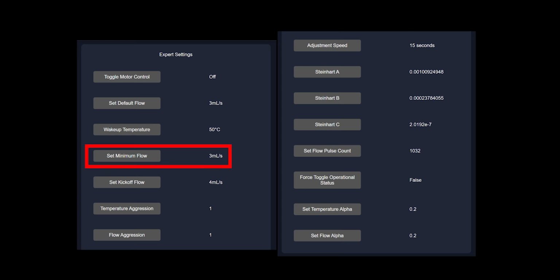The minimum flow is a hard limit where ATACC will make sure the flow never goes below this point. It is recommended that you set this to match the default flow. The kickoff flow is a flow target that ATACC will briefly regulate to when it comes into active mode for the very first time. It simply acts as a way to smoothen the transition when the still very first boils and the temperature shoots up. This number should be below the flow that ATACC normally has when regulating at its target temperature, while also being above the default flow.